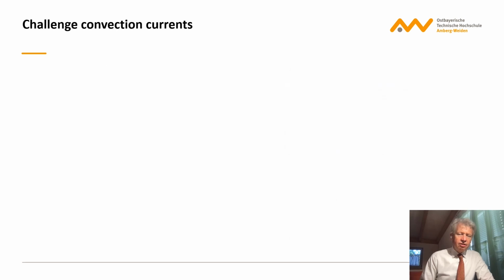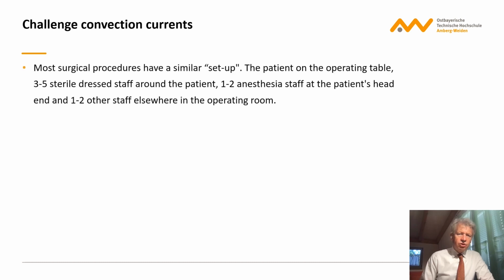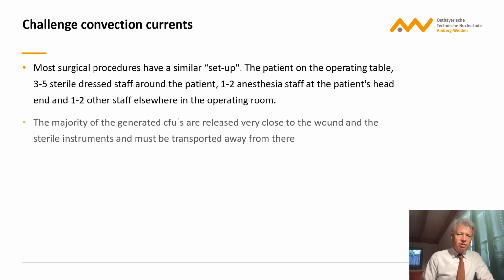The main challenge in this context is the convection currents. Most surgical procedures have a similar setup, the patient lying on the operating table, and then there is staff around the patient, anesthesia staff, and circulating staff in the room. The majority of the generated colony-forming units is released by the staff very close to the wound and must be transported away from there to avoid surgical site infections.